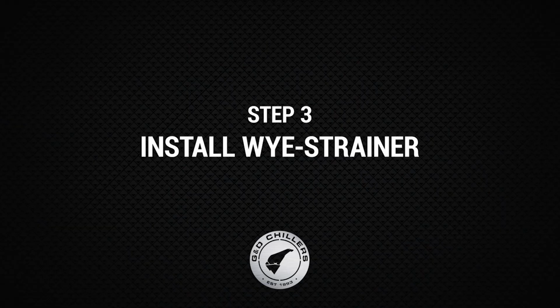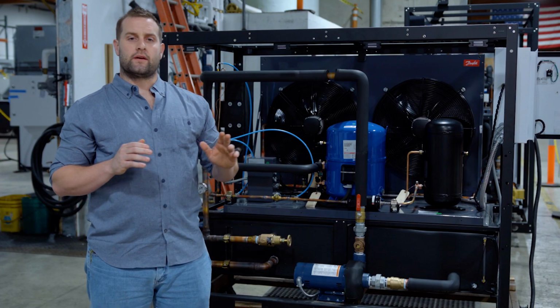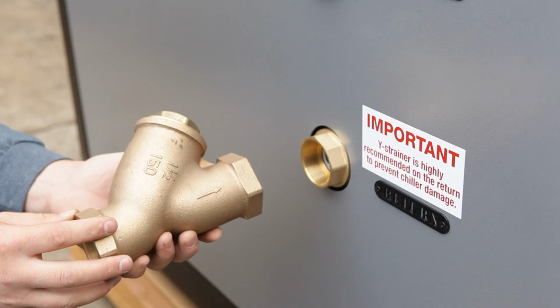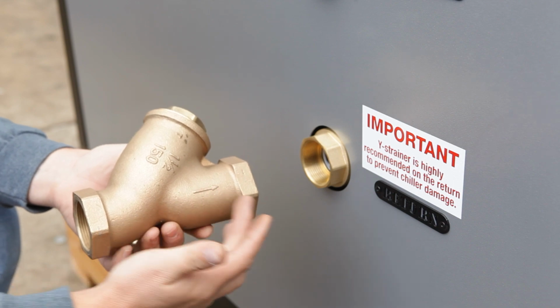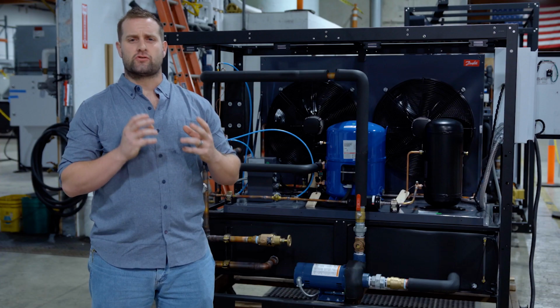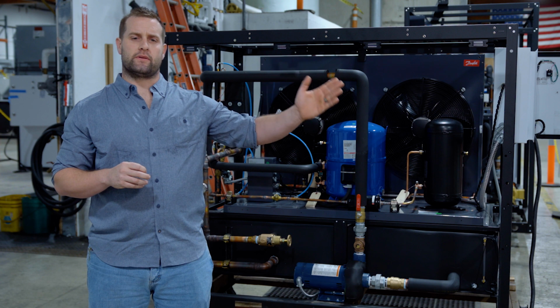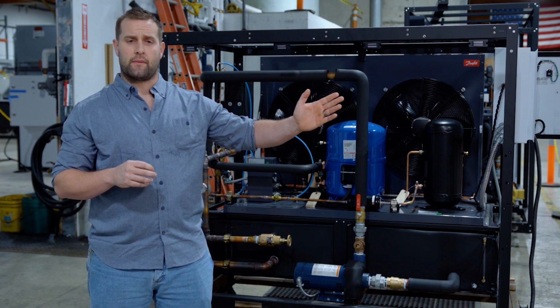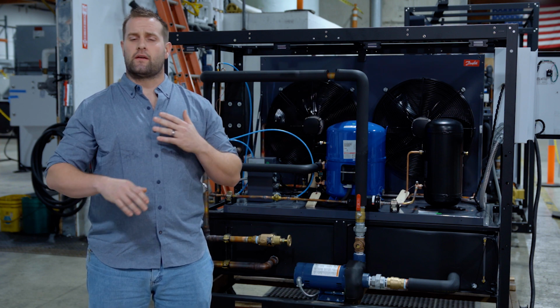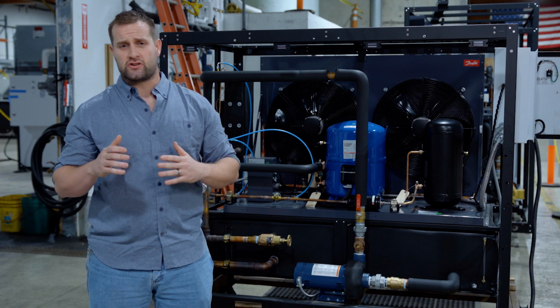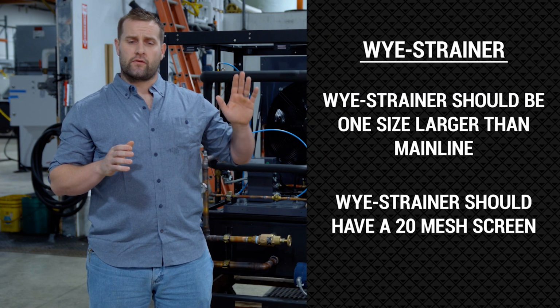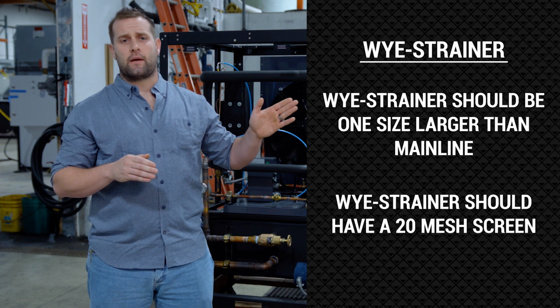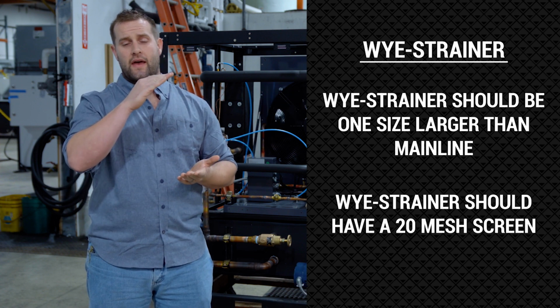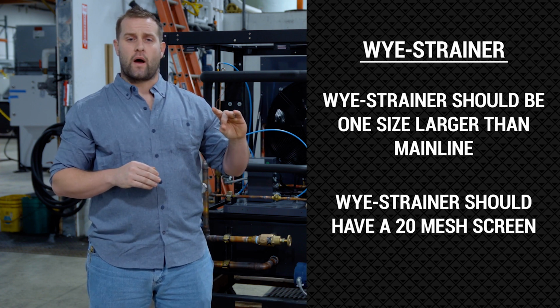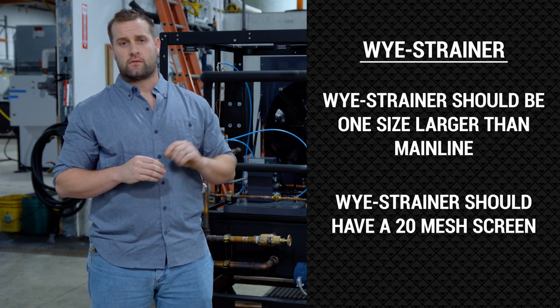The next step on the startup form, step 3, talks about a Y strainer. The Y strainer is going to be exterior of the chiller, on your return piping right by the chiller. It has a mesh screen in it, and it's going to filter out any particulates from your process piping so they don't get back to the chiller, where they can foul the heat exchanger and cause issues. To size it, whatever size your main line is for your process piping, you want to go one size above that. And the screen inside the Y strainer needs to be a 20 mesh screen.